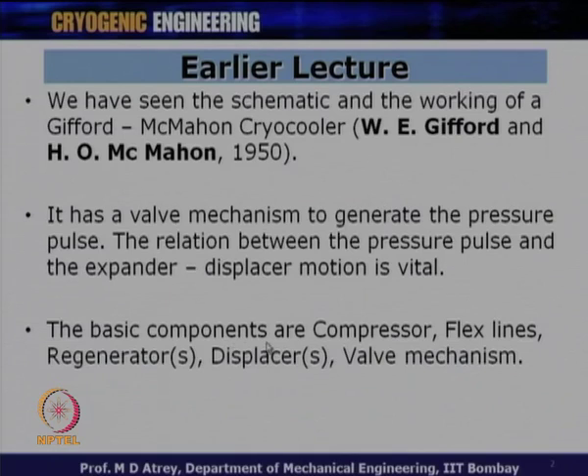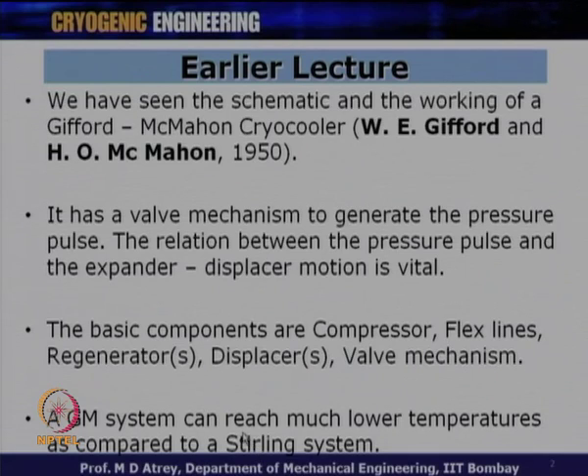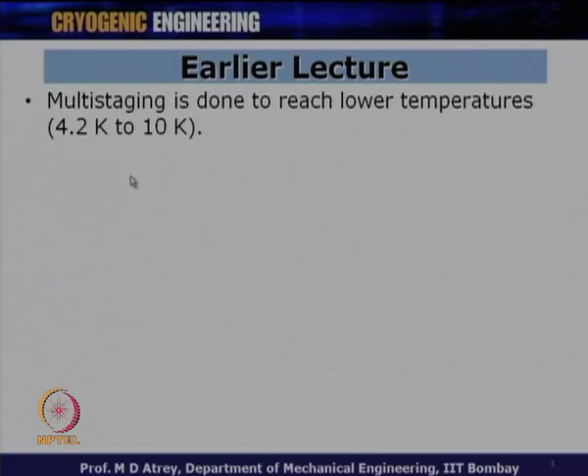The basic components of the GM cryocooler are compressor, flex lines, regenerator, displacer, valve mechanism, etc. A GM system can reach much lower temperatures compared to a Stirling system. The difference is that GM has a valve and runs at a very low frequency of around 1 to 2 Hz, while Stirling operates without a valve at a much higher frequency. In GM cryocoolers, multi-staging is done to reach very low temperatures of around 4.2 K, which is the helium boiling point, and up to 10 K.